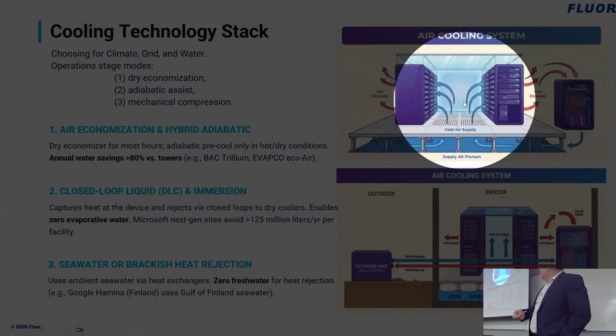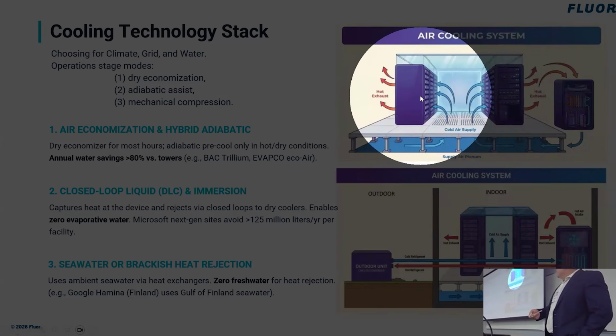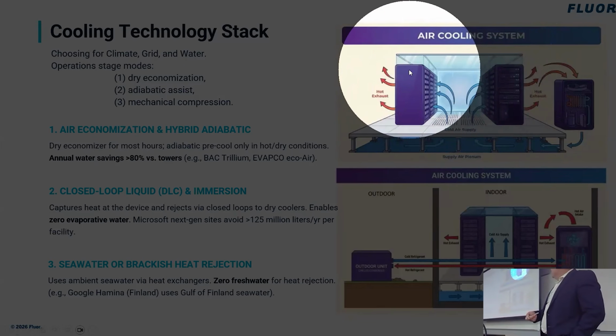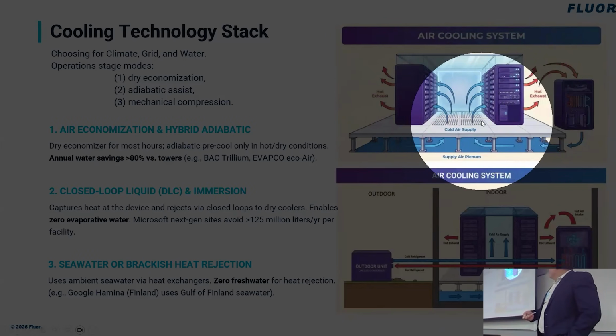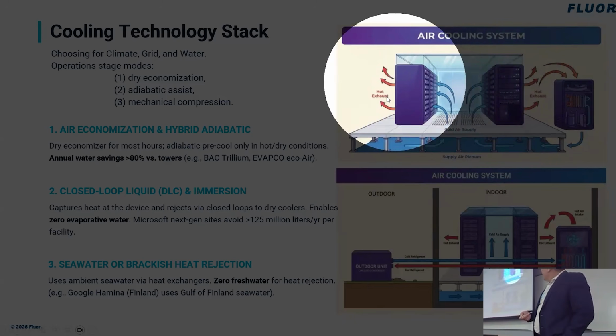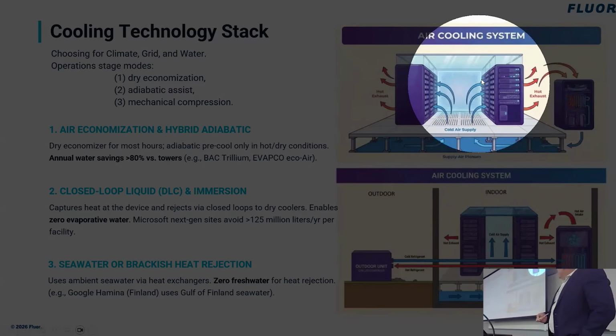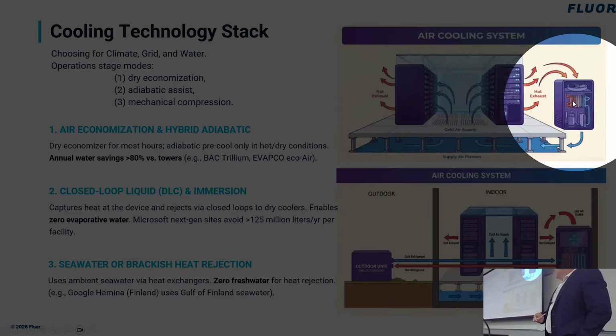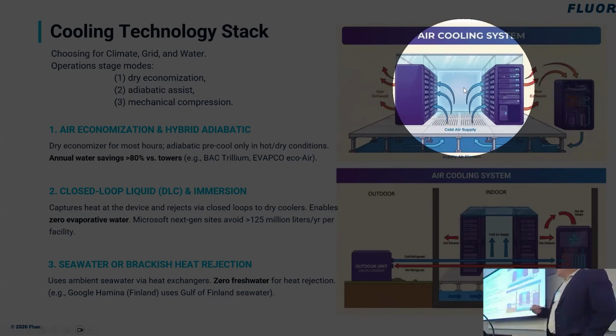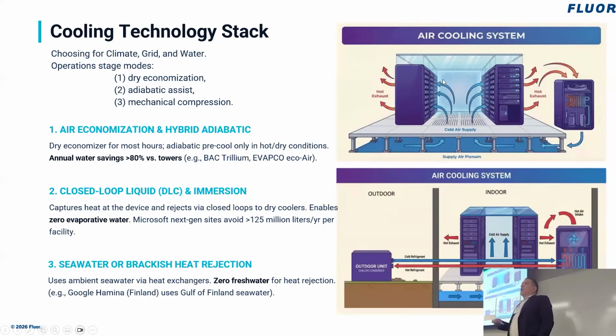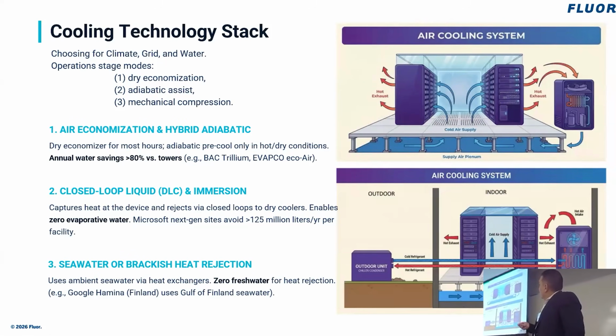In the optimization, when the heat started increasing because of the increasing density of the rack, some optimizations were put in place. For example, isolating what's called a cold aisle, to avoid mixing hot air with cold air. That was an optimization. And normally the rear heat exchanger was placed close to the source of the heat. So those were strategies to minimize and optimize heat recovery using only air.